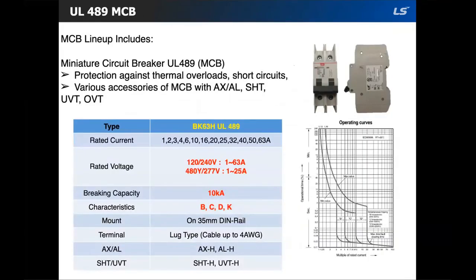And here is the same table for UL 489. One thing to remember, breaking capacity for 480Y/277 volt is 10K only from 1 to 25 amps. And same as 1077, these are mountable on 35mm DIN rail, and terminal type is the same. And then they also share the same aux contacts, shunt unit, and under voltage unit.